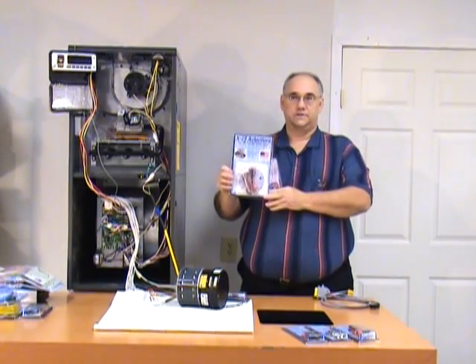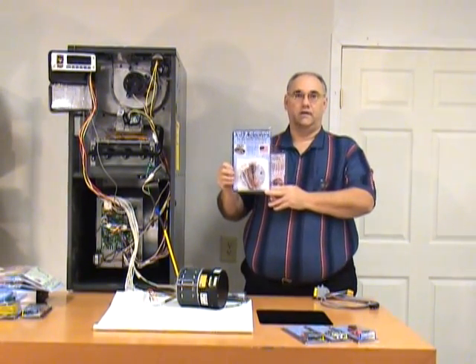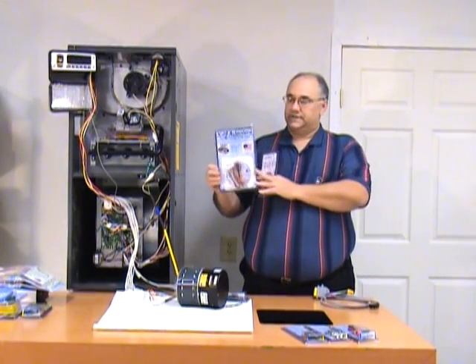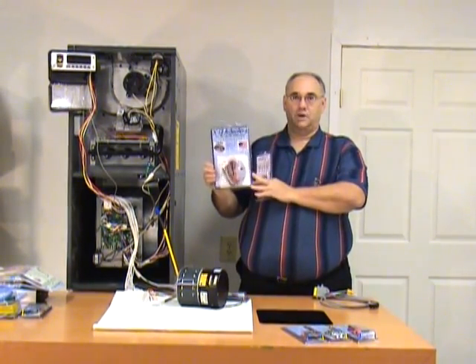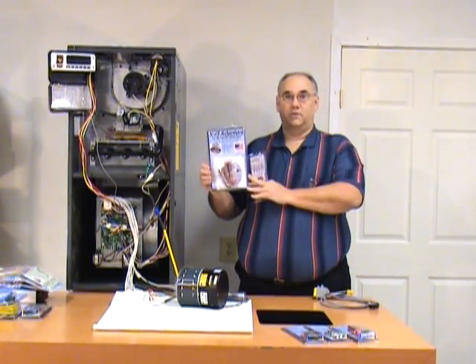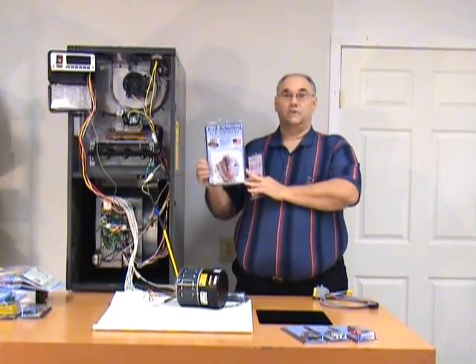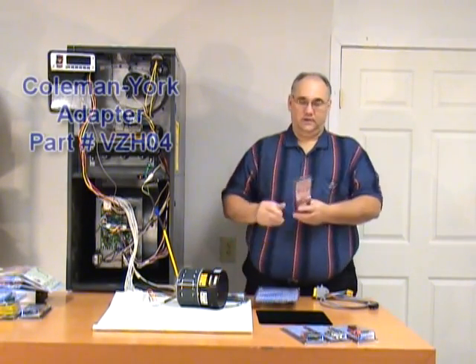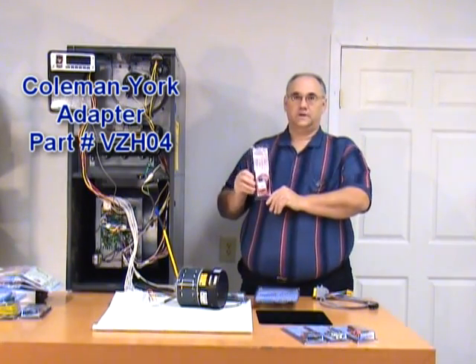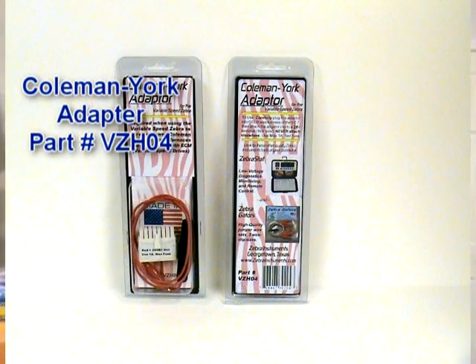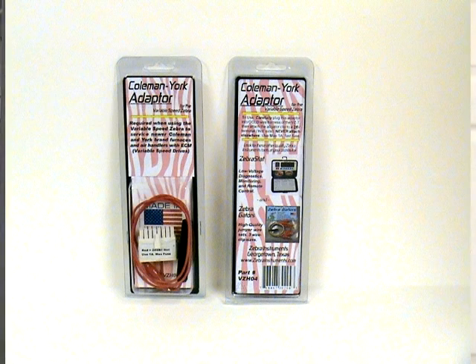They're starting to become very popular after January 2006 guidelines came out for higher SEER in furnaces and air handlers. This is an inexpensive way to be able to properly diagnose and monitor the signals going into and generate your own signals going into the X13 motors. The other adapters that we have available are the Coleman-York adapters. What we found is Coleman doesn't always run a 24-volt hot power supply line to the ECM motor. The variable speed Zebra needs that to be able to work. This gives you a safe access so that you can hook on a 24-volt hot line and run your variable speed Zebra.